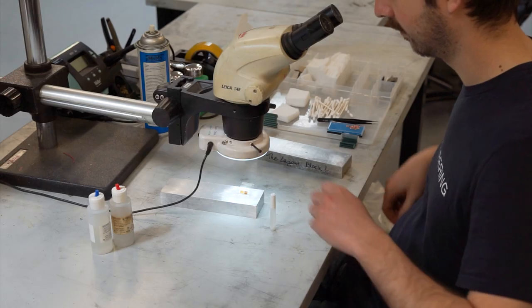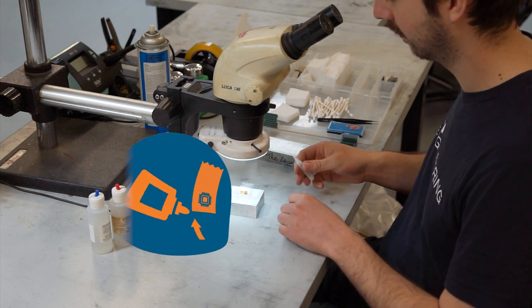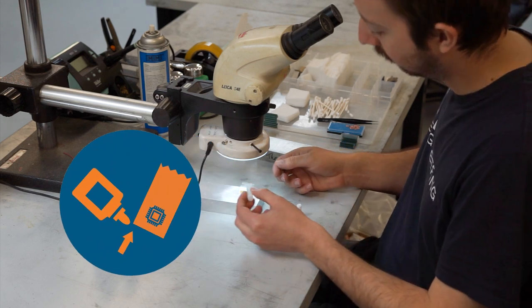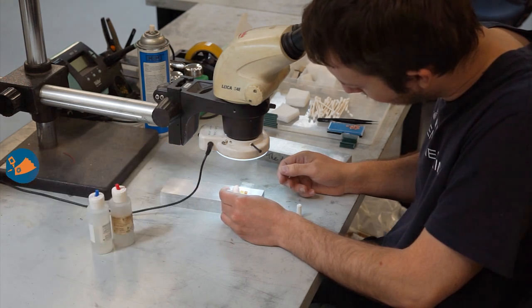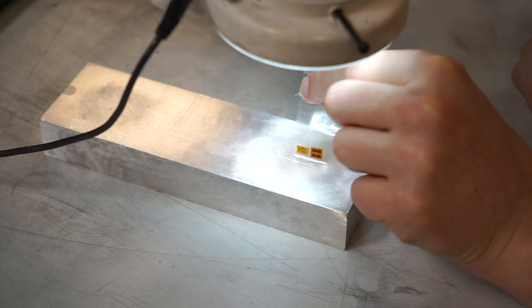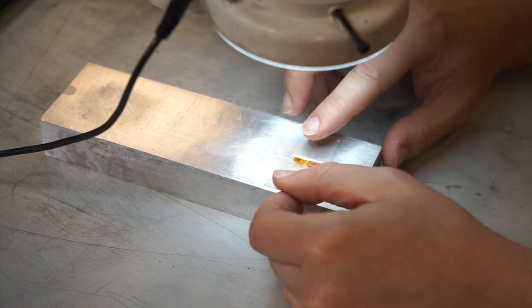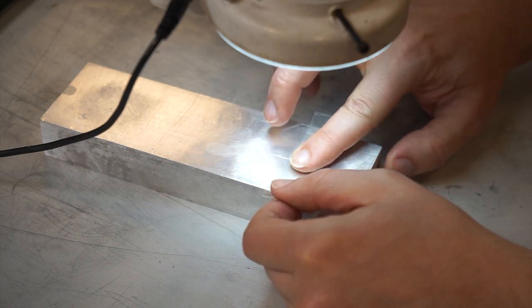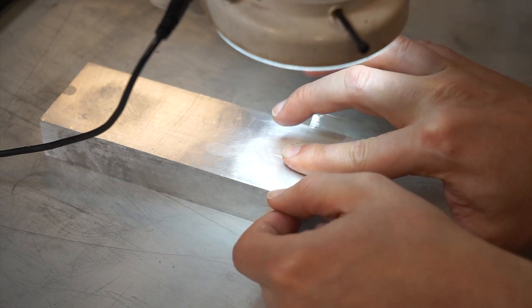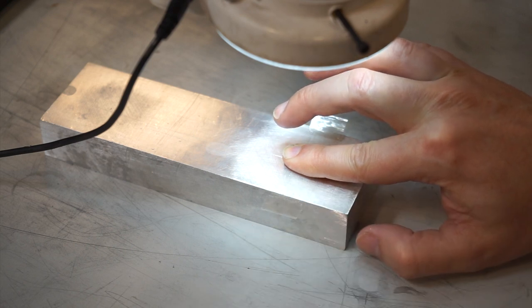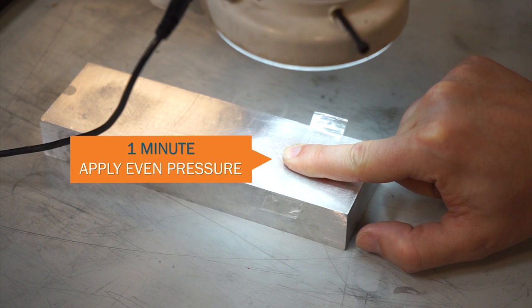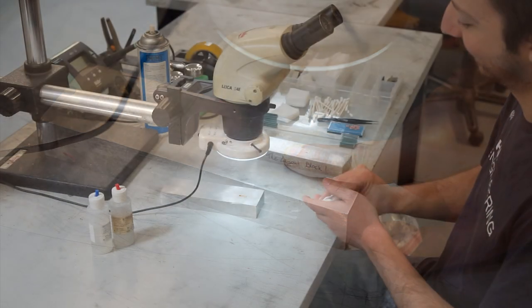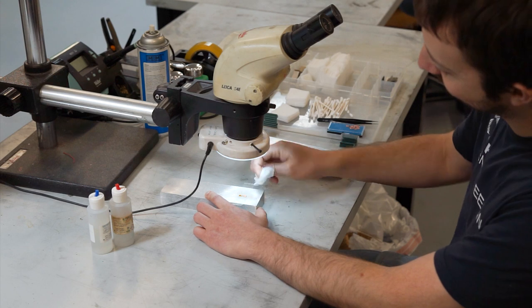Next, place one drop of adhesive at the junction of the tape and specimen. Holding the tape taut, slide your fingers over the gauge assembly, sticking the gauge down to the surface. Press vertically down on the gauge with your index finger for one whole minute. Keeping pressure is crucial to ensure no bubbles exist under the gauge. Wipe away excess glue.